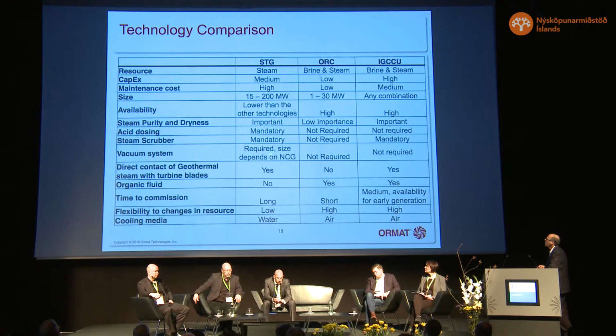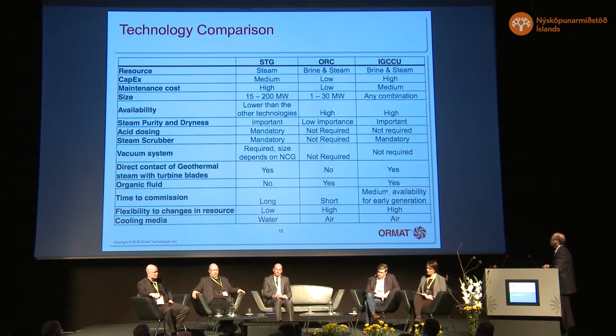Vacuum system is required only here, and the size depends upon the NCG, the steam pressure for the ejectors, and the cooling water for the liquid vacuum pump. Only in the ORCs there is no direct contact between the steam and the turbine. We believe that ORC has a shorter time to commission, and the IGCCU probably can be built in stages. Flexibility to changes in resource with the ORC and the IGCCU is higher than in the case of the STG.